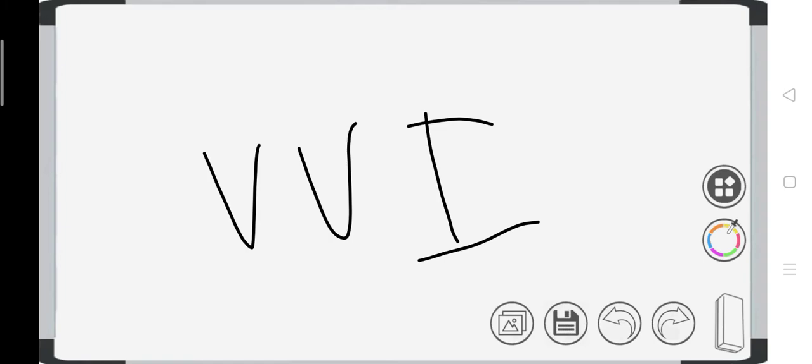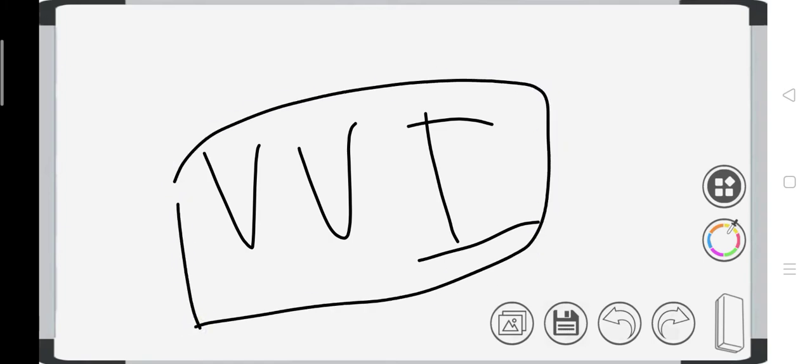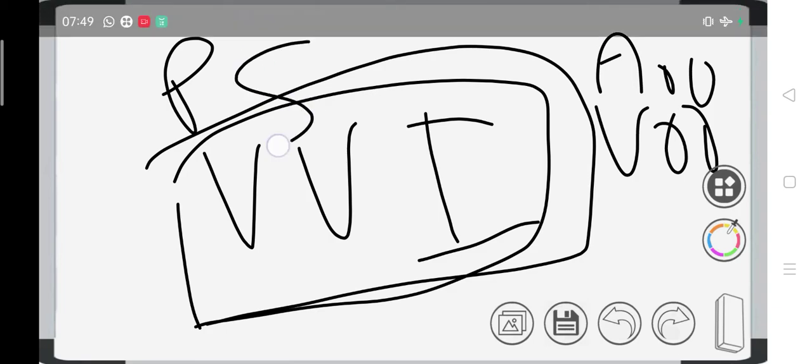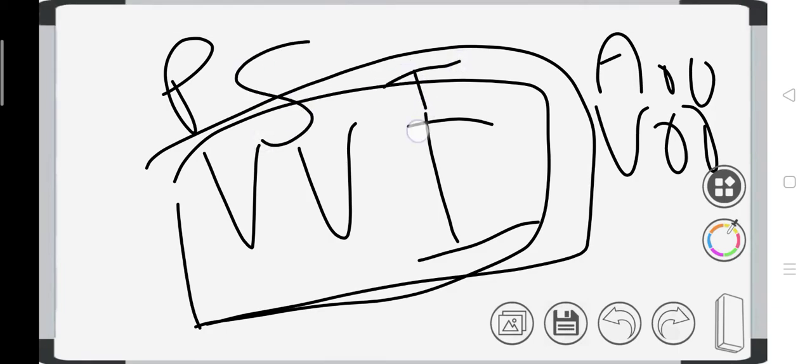The simplest modes, other than the magnet we have put, are VOO or AOO, but other than that, what we usually use is the VVI mode. So what is VVI mode? The first letter is pace, the second letter is sense, and the third letter I is inhibition. Most of the time we use inhibition, because inhibition doesn't need electricity, so the battery, the generator, will not die early.